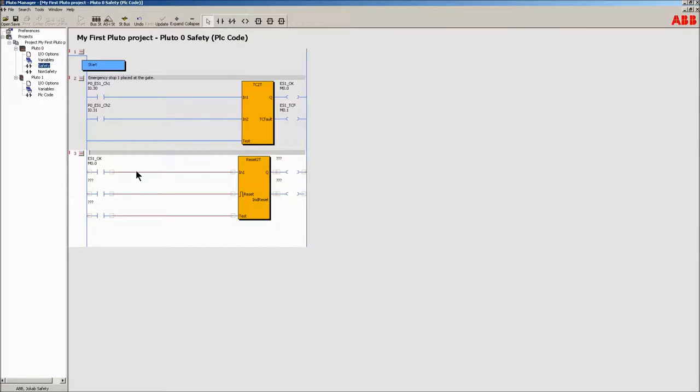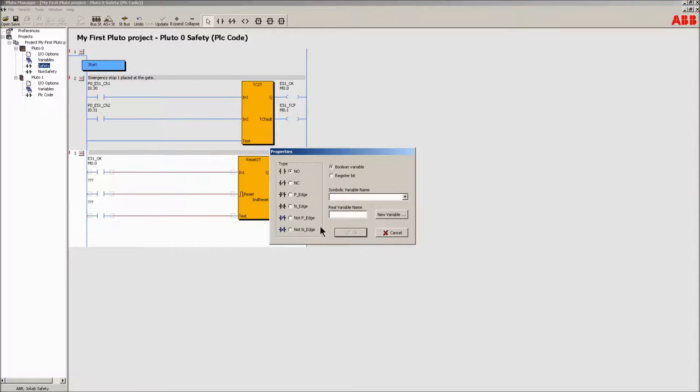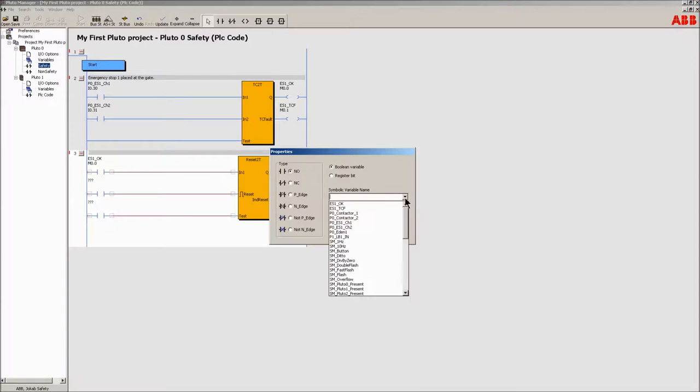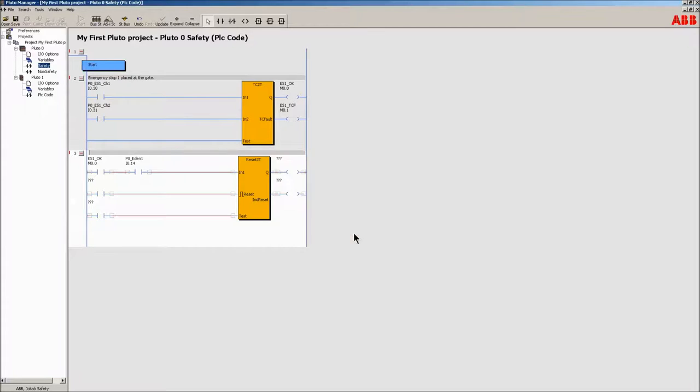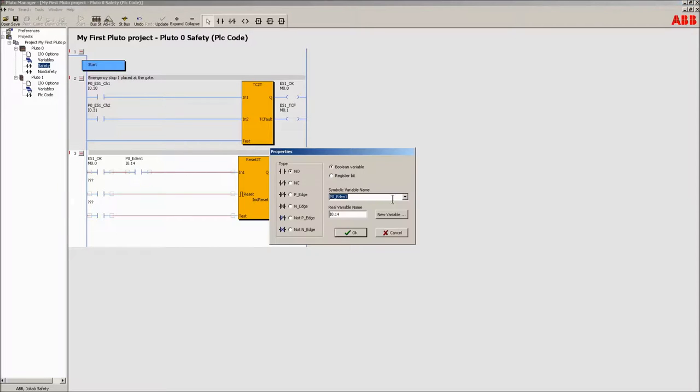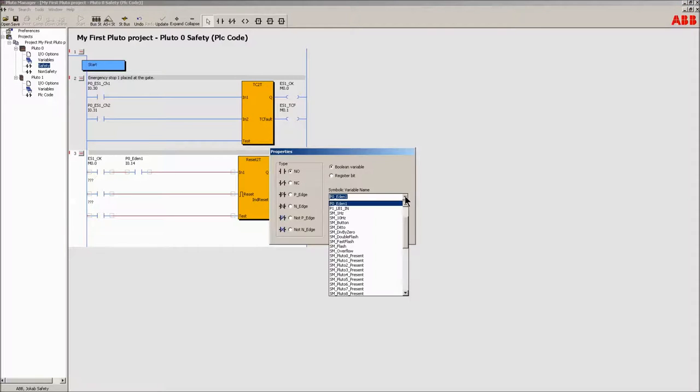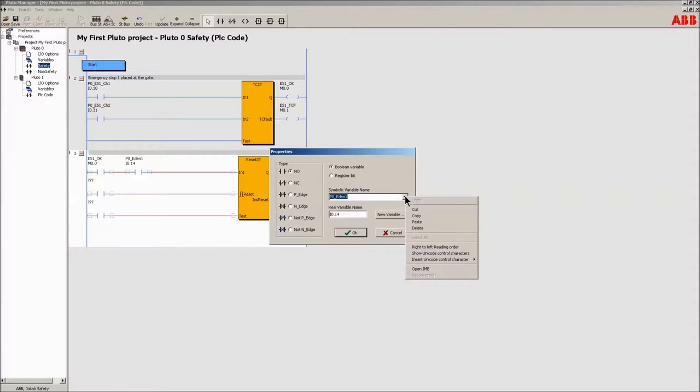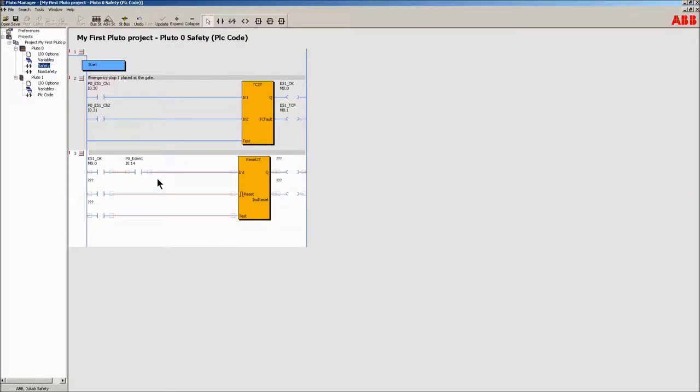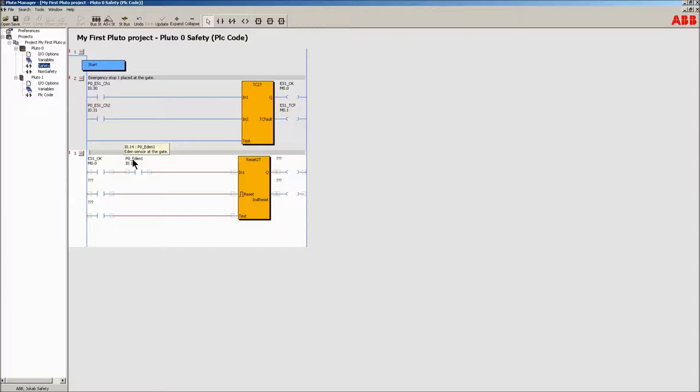Add the emergency stop OK bit to the input in one of the block by double-clicking on the contact. The gate, which is monitored by the EDIN sensor, must also be added to the network. Do so by clicking on the contact in the upper part and put it in place. Select the EDIN sensor. Its dynamic signal is already evaluated as on or off by the two processors inside the Pluto unit. There is no need to run it through a special block.